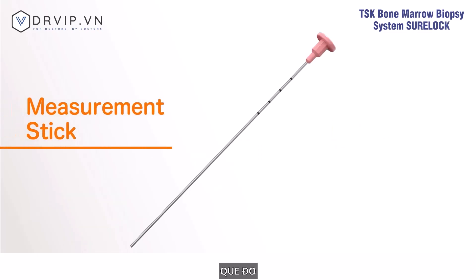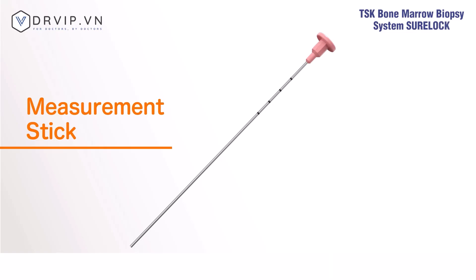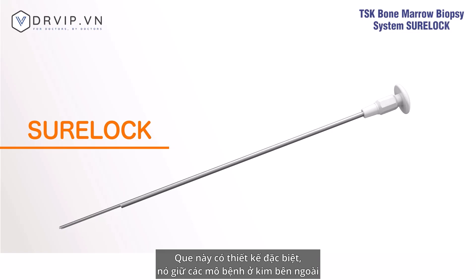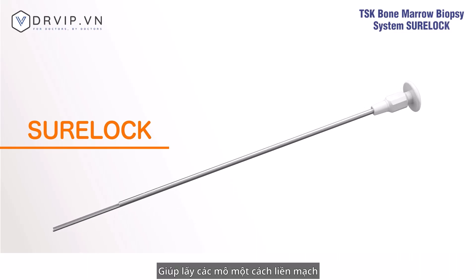The measurement stick has one centimeter markings that allow confirmation of the approximate length of the tissue collected in the outer needle. Using our specially designed tubing, the Surelock holds the tissue collected in the outer needle handle, allowing tissue to be collected intact.